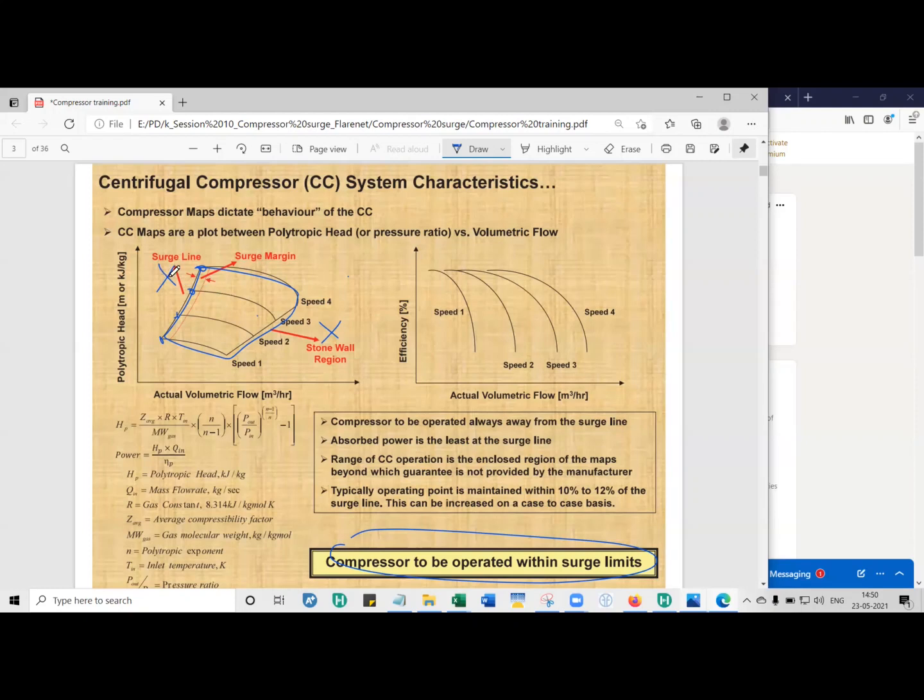Operating into the surge line region. So what we do is, let me just erase it first. What we do is we maintain a certain margin here. This is called SLL, surge limit line. So the surge limit line is the point at which the anti-surge system will kick in.